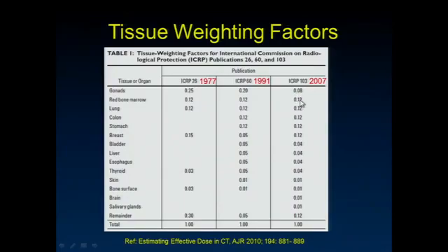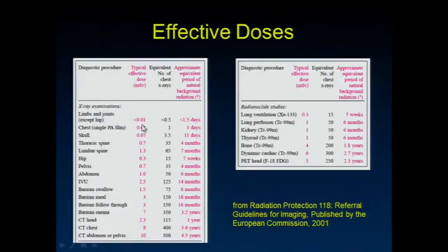The bone marrow, we could calculate the dose of the red bone marrow in the thoracic spine and multiply that by the 0.12 factor. And certainly the lung gets a dose, and if we knew what that dose was, we could multiply that by the 0.12. The brain doesn't really see any dose in a chest x-ray, so we'd be multiplying this 0.01 times a 0 term, and we'd add those up, and we'd get a number for a chest x-ray right in this order right here. And now if we did a CT scan of the abdomen or pelvis, we could do a similar thing, applying the doses of the individual organs received by their appropriate weighting factors and then adding those up. And doing that gives us this table, where we can now start to compare things to each other. But realize this comparison is at best an approximation, going through this measurement of effective dose that we talked about. Does that make sense to everyone?